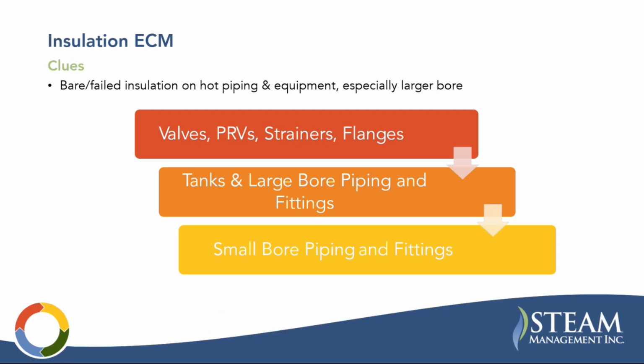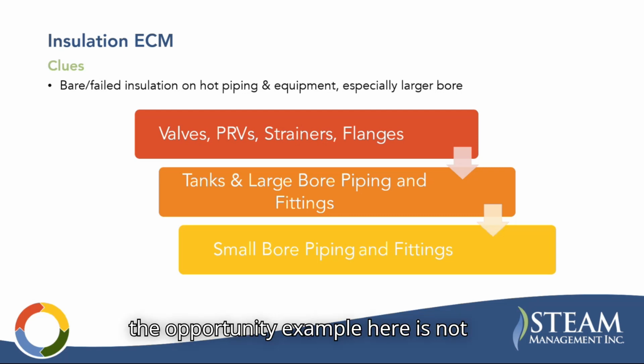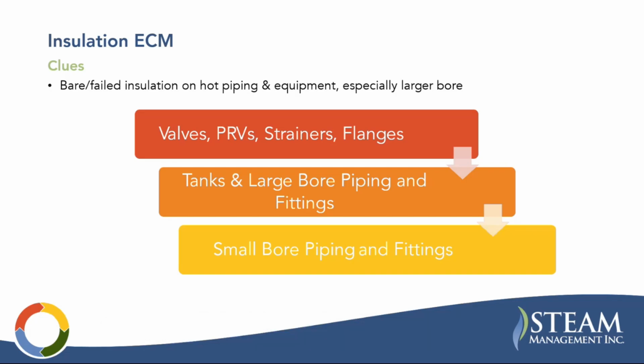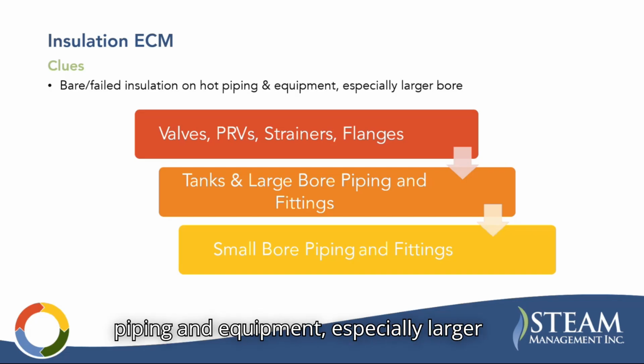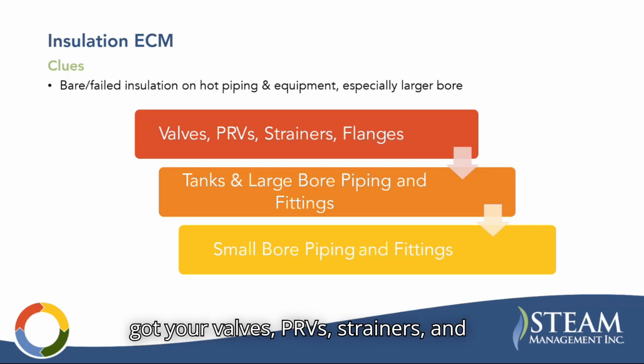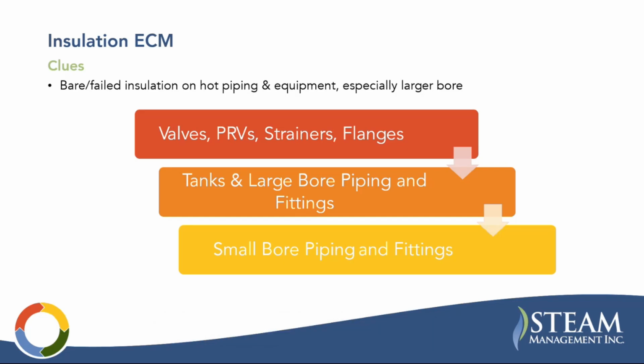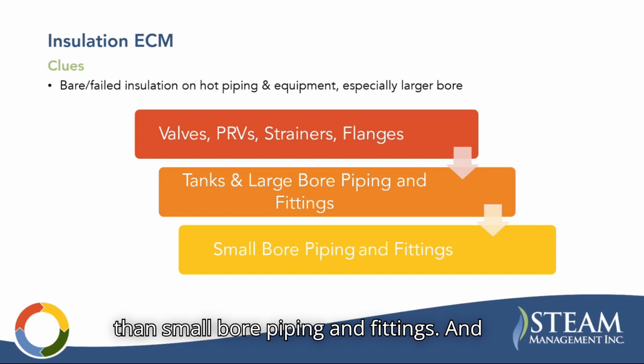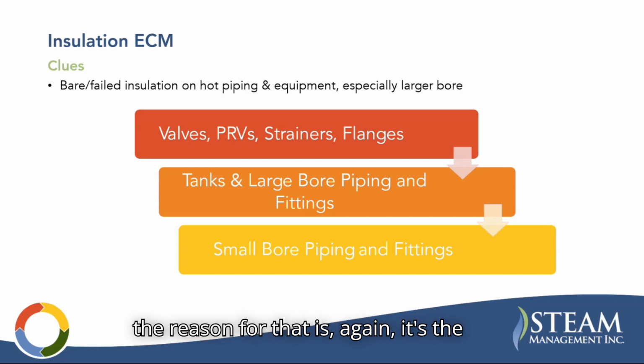As for insulation, the clues here are bare or failed insulation on hot piping and equipment, especially larger bore equipment. So this is kind of your hierarchy of priorities, right? You've got your valves, PRVs, strainers, and flanges. Those are a priority because they are a lot of surface area for the amount of insulation required. And then tanks and large bore piping and fittings are going to be a better payback than small bore piping and fittings. And the reason for that is, again, it's the surface area compared to the amount of insulation and the labor required to install that.